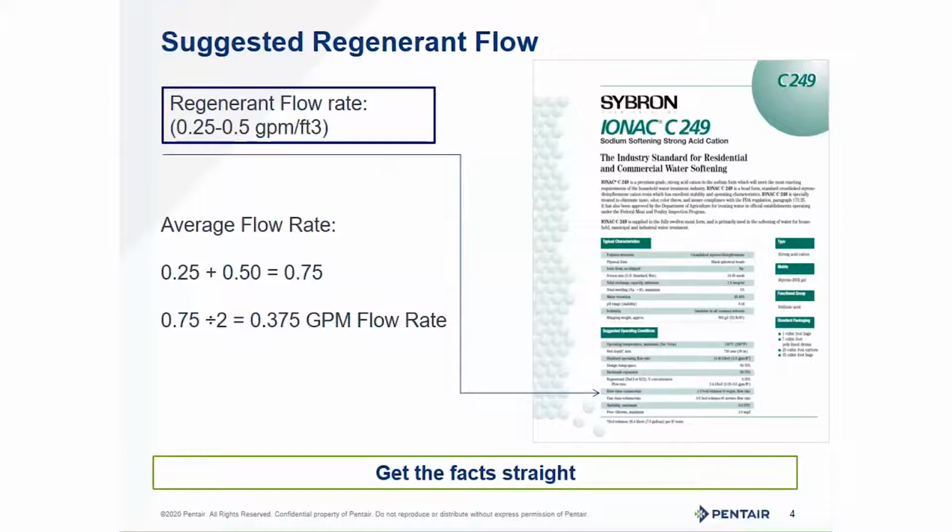But they've given you a range. So how do we decide which end of the range to use? Well, with water treatment devices, we are always going to want to shoot for the heart cut of the range. Why? Because that leaves us wiggle room up and down for changes in pressure and variations in water chemistry.